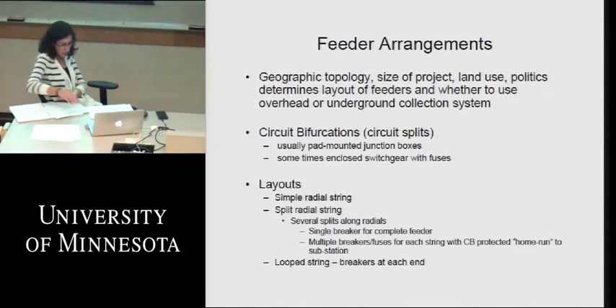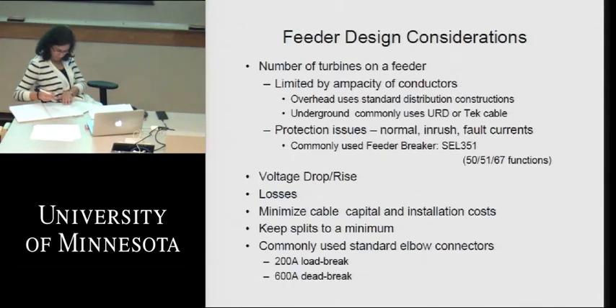Some of the other considerations for these collection feeder cables: the number of turbines you can get on a feeder is really dictated by the ampacity of the conductors you're using. We generally use aluminum type of underground cable in either standard underground residential distribution (URD) type of cable constructions, or in Canada they use this TECK cable. But these are generally just your normal underground insulated type of cables here. The cables have to be protected from normal operating currents, inrush currents, and fault currents, obviously here. And the Schweitzer 351 is the most commonly used relay for those feeder breakers.